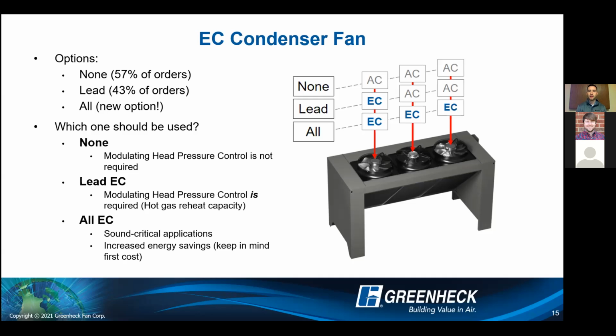So if we think about all AC motors, for example, we have part load conditions. Maybe we don't have as much heat in the system. Well, if we don't have as much heat in the system and we have all AC motors, that AC motor is going to turn all the way on and reject all that heat, even if we don't need all that heat rejected. So now because we rejected all that heat out of that condensing section, we don't have enough hot gas going back through our reheat coil. If we had the lead EC motor, now we can turn that on at minimum, turn it all the way down, and then we can reject just enough heat out of the condensing section and divert most of that heat back to that reheat coil. So during part load conditions, we can get enough capacity to get back up to that space set point that we want to see.